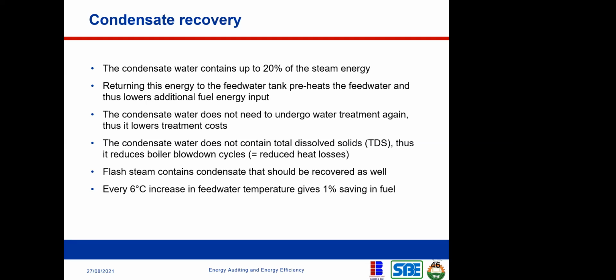Then every 6 degrees centigrade increase in feed water temperature gives 1% savings in fuel. I cannot overstate this, right? Where I keep talking about recovering the heat from your exhaust pipe and then using it to preheat the water, your feed water that is going back to your boiler. Once you do that, you begin to reduce the amount of fuel you need to burn to raise the temperature of that water from 20 or 25 or 30 to 100.